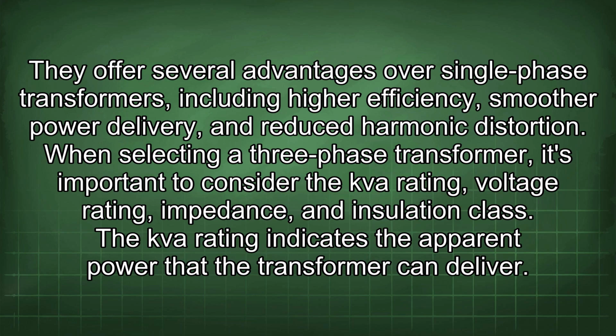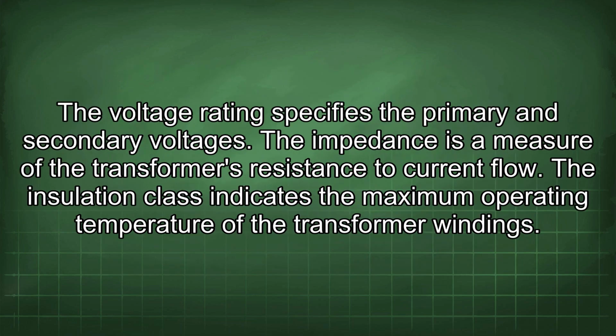When selecting a three-phase transformer, it's important to consider the kVA rating, voltage rating, impedance, and insulation class. The kVA rating indicates the apparent power that the transformer can deliver. The voltage rating specifies the primary and secondary voltages. The impedance is a measure of the transformer's resistance to current flow. The insulation class indicates the maximum operating temperature of the transformer windings.